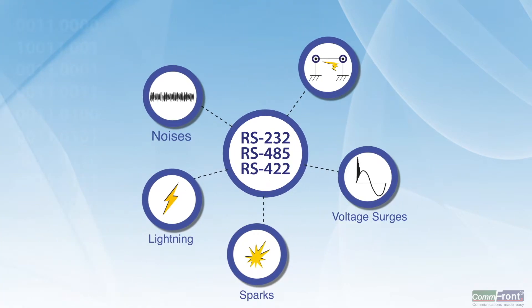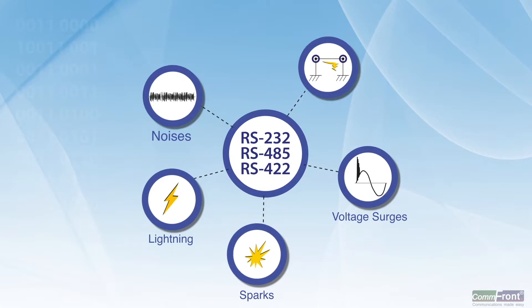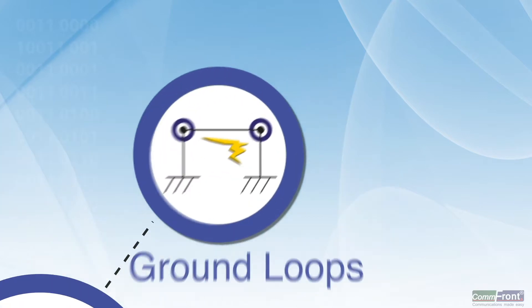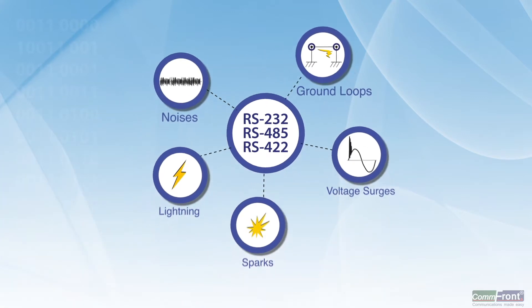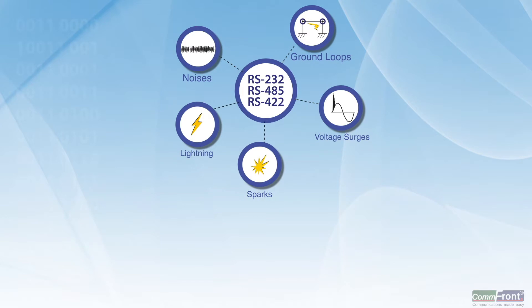Second, because the ground potential at different nodes could be different, significant ground currents could flow through the path of least resistance via the common earth ground, causing the ground loops problem. There are a few methods of voltage and current surge protection in the industry.